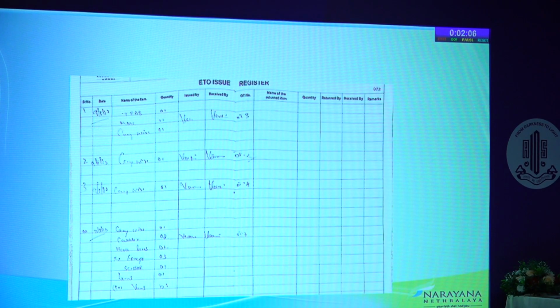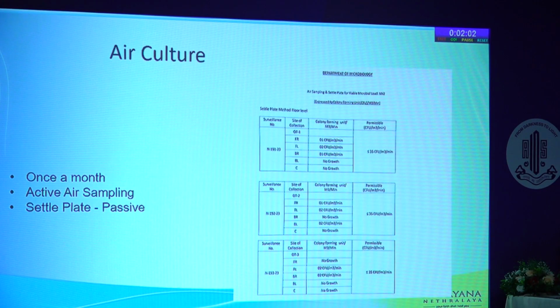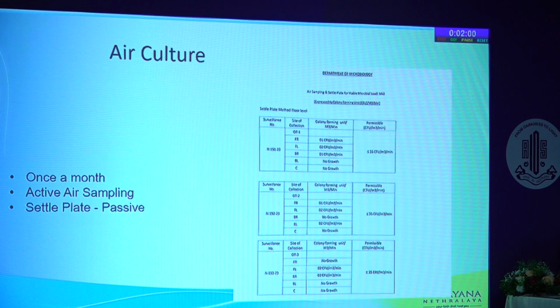Same thing with ETO, where it was issued, what was issued, which patient it was used. Air culture, we do once a month. We do active air sampling as well as settle plate method. So settle plate, typically all corners of OT and center.